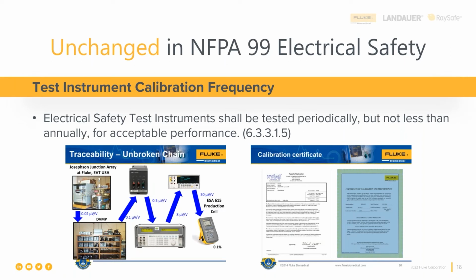And also that you should request a traceable test report, not just a certificate of calibration, because the complete report lists the transfer standards or primary standards that were used during the factory calibration, and also the uncertainties of measurement for each and every test that's performed. And the uncertainties of measurement may add to the specification pass-fail criteria, and you may discover that calibration corrective action may be required sooner rather than you think.